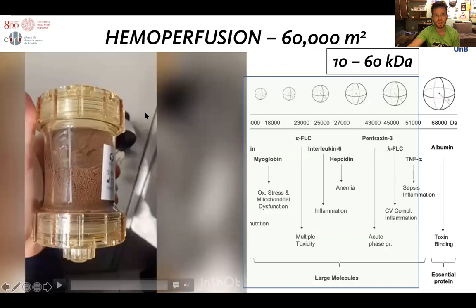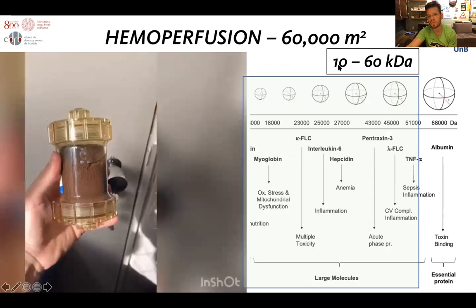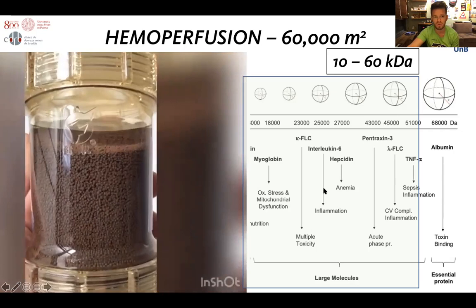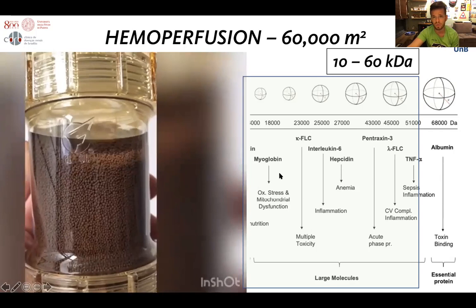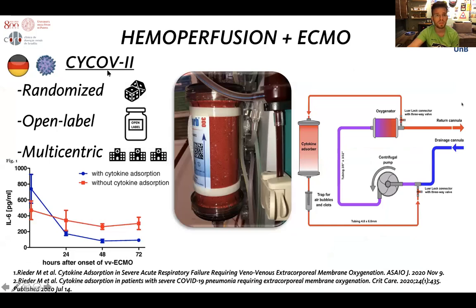This is the CytoSorb cartridge we are talking about. It contains microspheres — the beads — capable of removing molecules from 10 to 60 kilodaltons, which covers almost all pro-inflammatory molecules and cytokines. For instance, IL-6 has 21 kilodaltons, TNF-alpha has 51 kilodaltons, and others fall within this range. The surface area for adsorption in one cartridge is 60,000 square meters — equivalent to about 12 Maracanã stadiums.